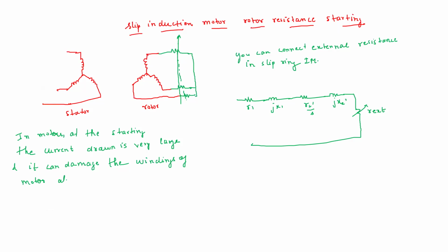It causes voltage dip. You will see that in induction motor, the starting current is at least 8 to 10 times of the full load current. So it is very large, right? Very large than the rated value.